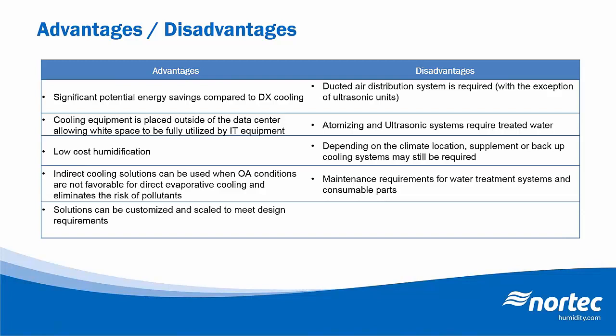Now, as I mentioned, atomizing nozzle systems and ultrasonic systems do require treated water. So in addition to the cost of the water treatment equipment, you need to consider the water consumption as well. Over the last few years, water usage efficiency has become a very important metric that data center designers are looking at more closely, as well as energy efficiency, especially in areas that are experiencing droughts. If we look at an RO system, the recovery rates can be as low as about 50%. That means for every gallon of treated water that we need out of the system, we would need to supply 2 gallons of untreated water. Now, there are high efficiency membranes available that can help reduce that wastewater, but the cost of the water treatment still needs to be considered, especially for large capacity systems.